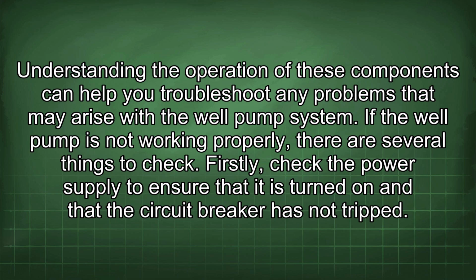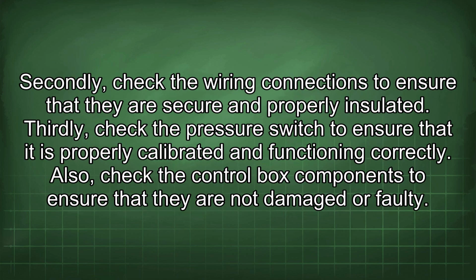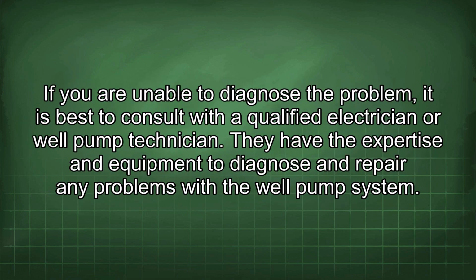If the well pump is not working properly, there are several things to check. Firstly, check the power supply to ensure that it is turned on and that the circuit breaker has not tripped. Secondly, check the wiring connections to ensure that they are secure and properly insulated. Thirdly, check the pressure switch to ensure that it is properly calibrated and functioning correctly. Also, check the control box components to ensure that they are not damaged or faulty. If you are unable to diagnose the problem, it is best to consult with a qualified electrician or well pump technician. They have the expertise and equipment to diagnose and repair any problems with the well pump system.